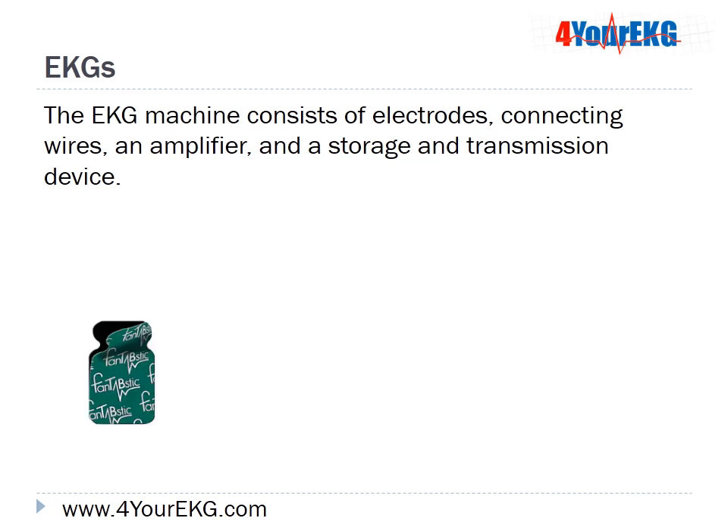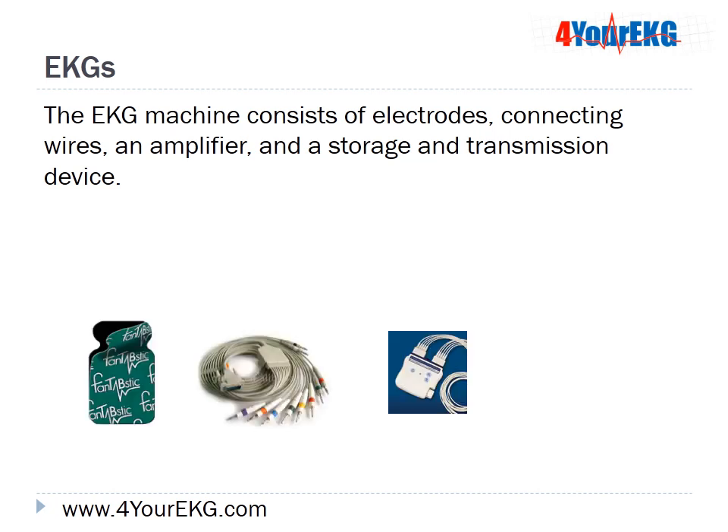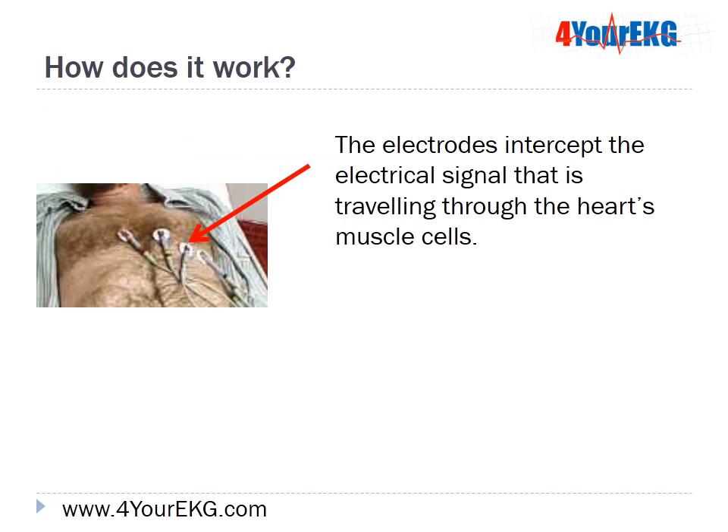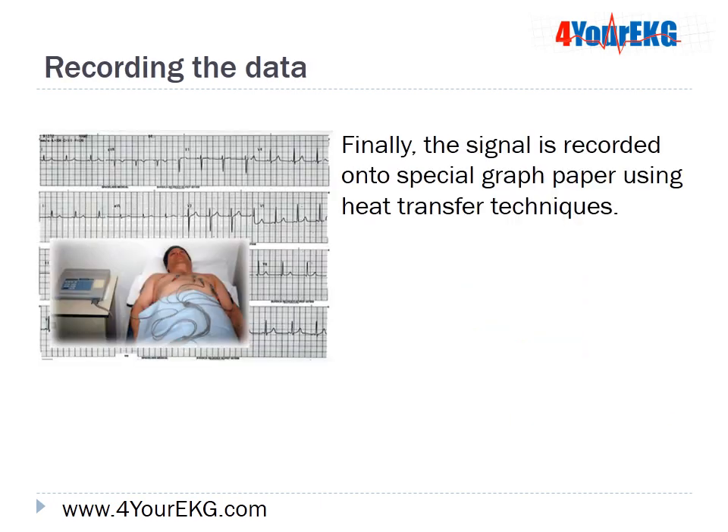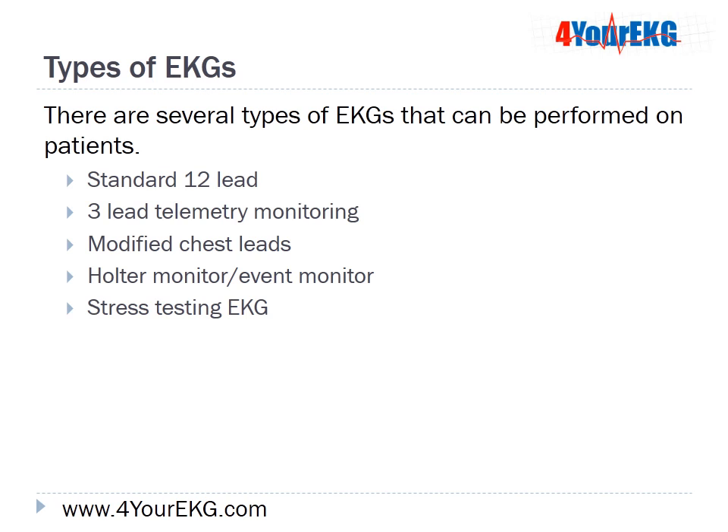The EKG machine consists of electrodes, connecting wires, an amplifier, and a storage and transmission device. The electrodes intercept the electrical signal traveling through the heart's muscle cells. This impulse travels through the lead wires to the amplifier, which makes the signal stronger, and the signal is then recorded onto special graph paper using heat transfer techniques. There are several types of EKGs: a standard 12-lead, 3-lead telemetry monitoring, modified chest leads, Holter monitors and event monitors, and stress testing EKGs.